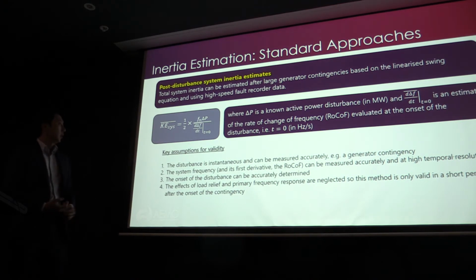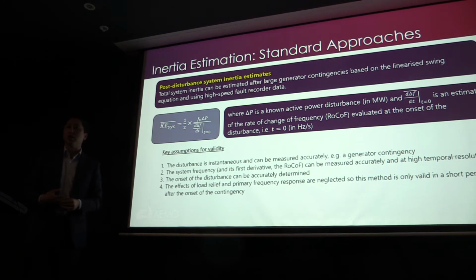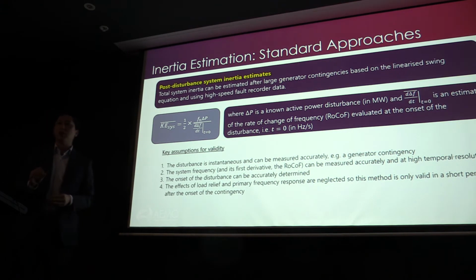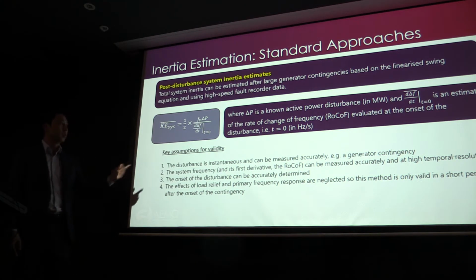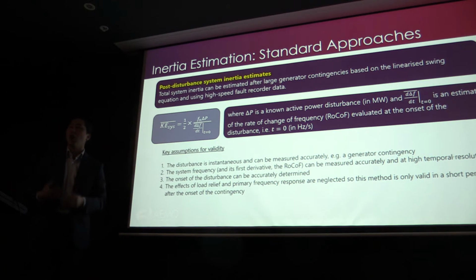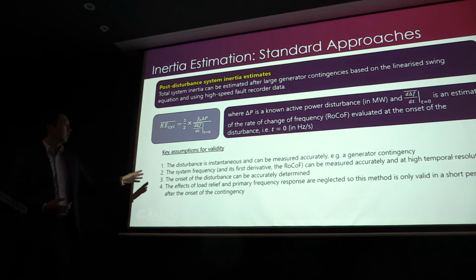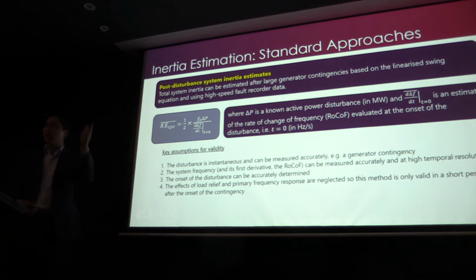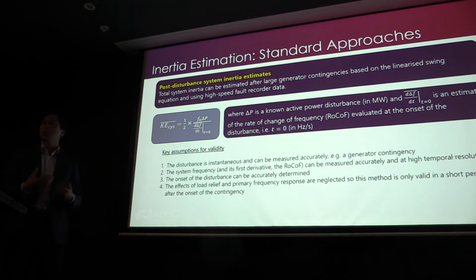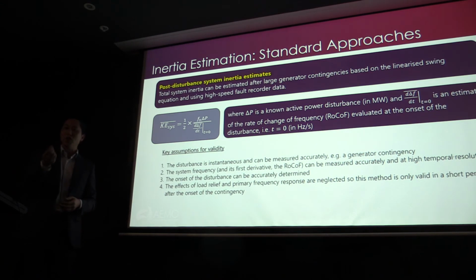The system frequency and its first derivative, the rate of change of frequency, have to be able to be measured accurately and at high temporal resolution. When I say high temporal resolution, I'm really talking about high-speed fault recorder data. You can't use, for example, 4-second SCADA to do this, because it's just too blocky. The resolution is not high enough. And the onset of the disturbance has to be accurately determined. You have to know when t equals 0 is, when the actual trip happened. That's why high-speed recorders are useful, because you can know exactly when the trip occurred.